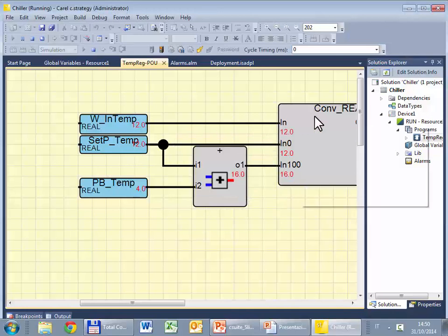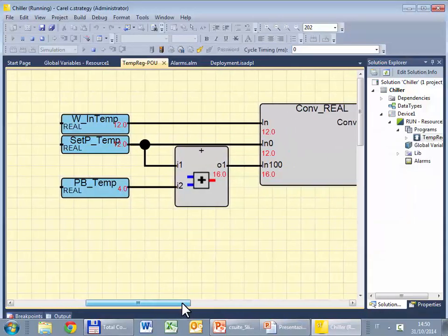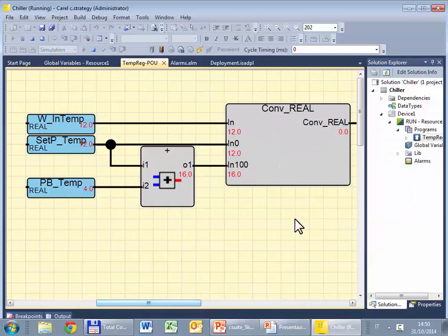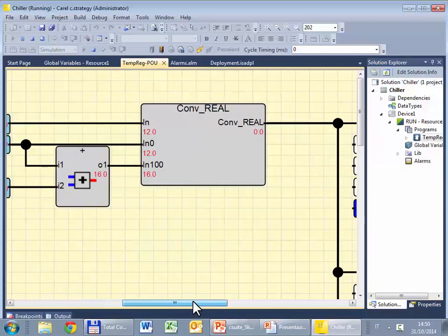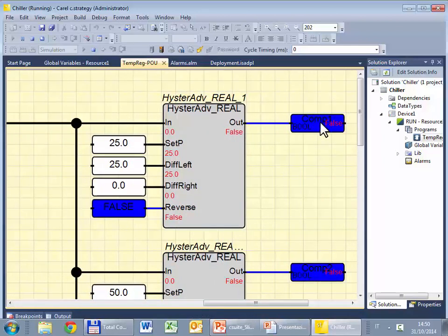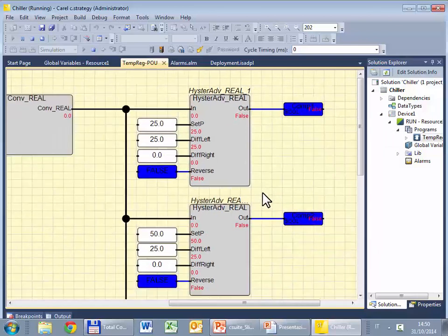So we expect that the block that creates the ramp returns 0, and in fact it returns 0, so the four stages should be off. In fact compressor 1 is false, as well as compressor 2 false, and also the others.